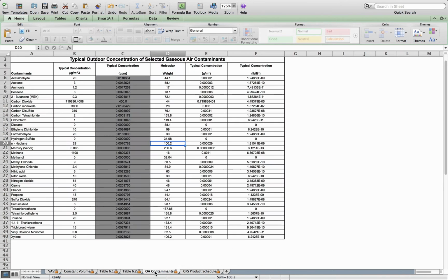And then just as a point of reference, you have an outside air contaminant tab, and you'll see typical concentrations. These values in the outside air were taken straight out of the ASHRAE handbook, and the handbook uses the average of the 5 worst air quality cities around the country, and these are pretty major metropolitan areas. However, if you know what the outside air contaminants are in your example or in your location, you can physically override these values, and you'll note that it's in parts per million.